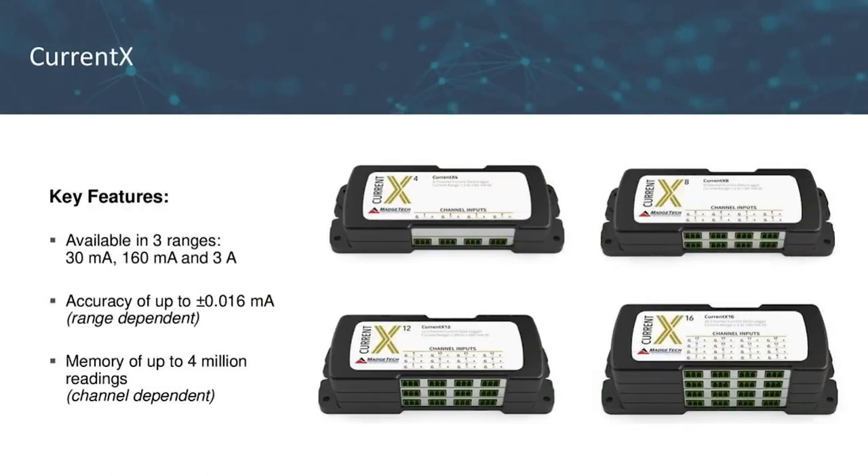This is our Current X series — low-level DC current data loggers available in three ranges: 30 milliamps, 160 milliamps, and 3 amps. They provide an accuracy of up to 0.016 milliamps and offer memory capacity of up to 4 million readings, channel dependent. These loggers accept current signals from sensors, transducers, and many other common current sources. Note that these are DC direct current loggers only.